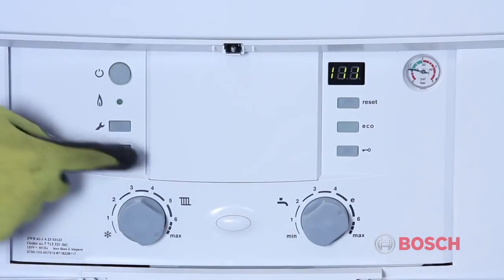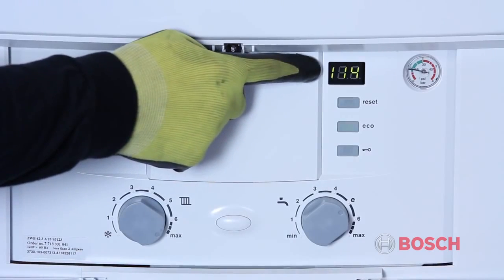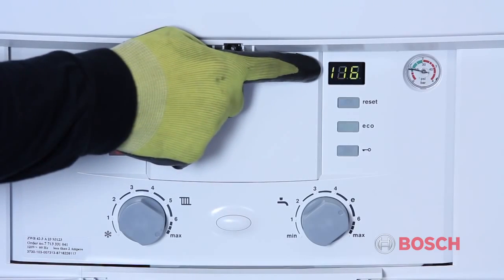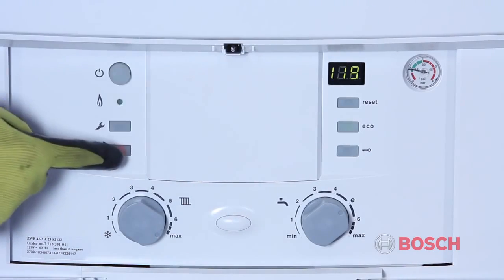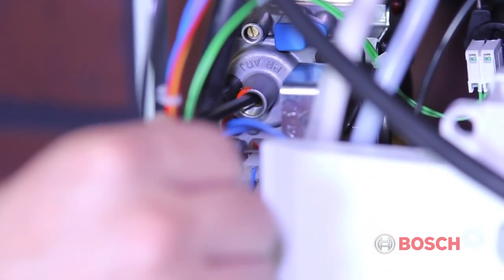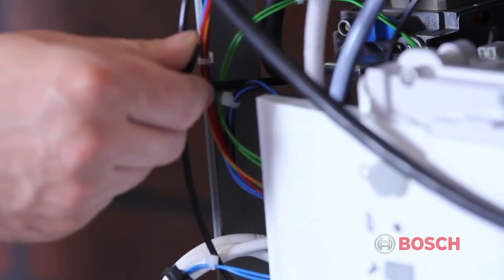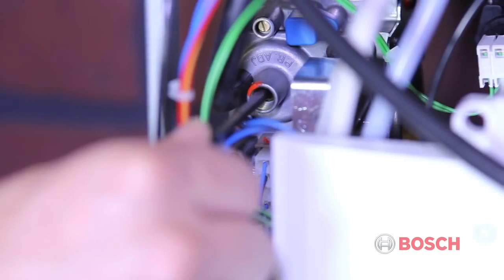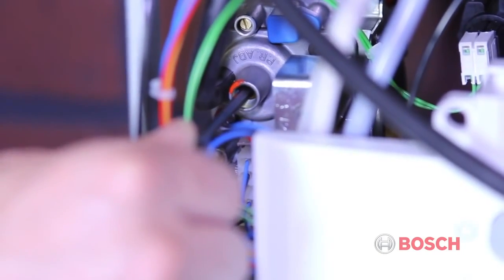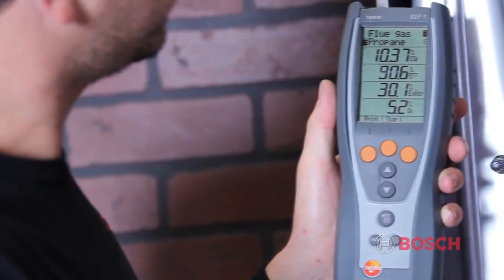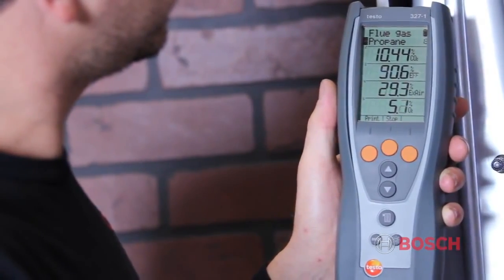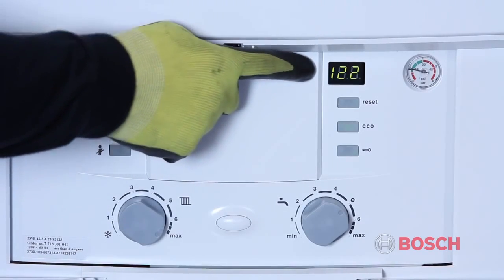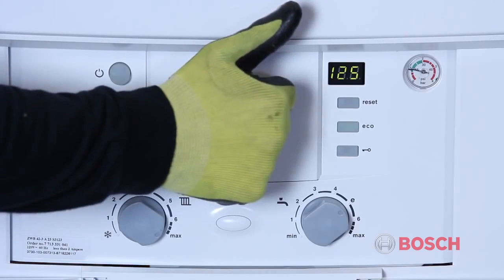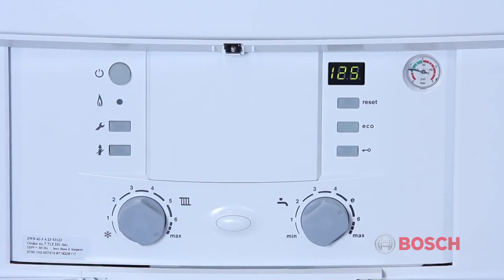To get into low fire mode, press and release the chimney sweep button once more. You will see 1 set of dashes. The low fire adjustment is made on the gas valve using a 4mm Allen wrench. Do not leave the Allen wrench in place when making adjustments. As you can see from the combustion analyzer, we are at 10.4% CO2. To return to normal operation, press and release the button 1 last time. This will return you to normal operation.